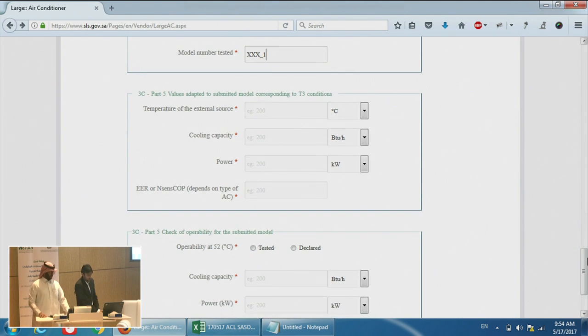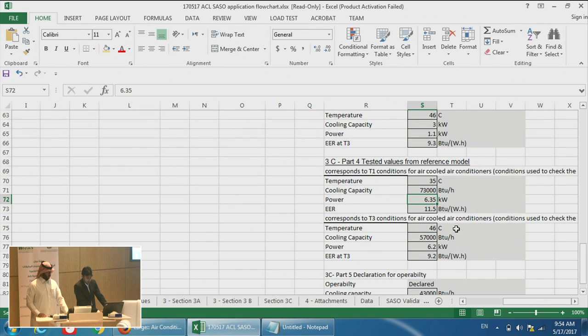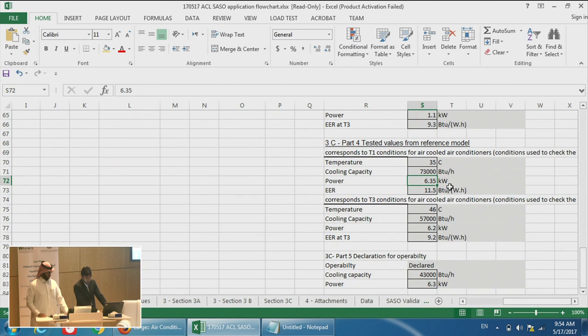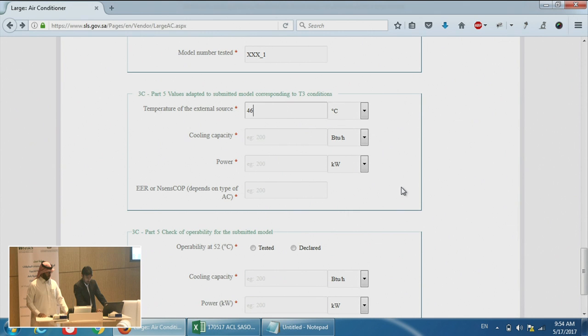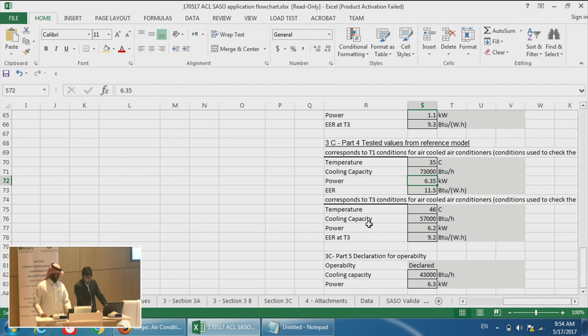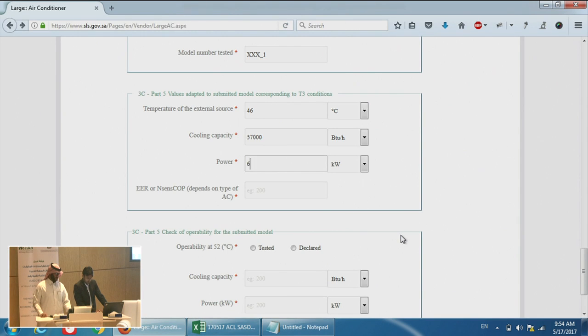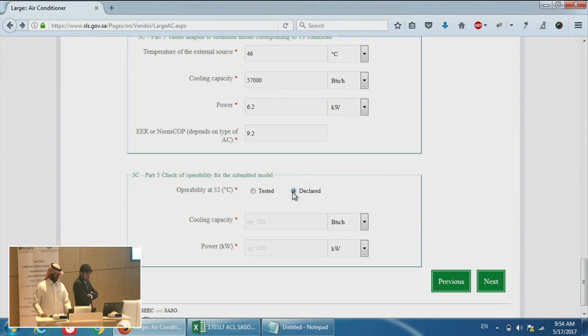3C Part 5, values adopted to the submitted model corresponding to T3 conditions. These are the three values: 46, 57,000. Power is 6.2 and EER is 9.2, as declared. 3C Part 5, check of operability for the submitted model: cooling capacity 57,000, power 6.2.